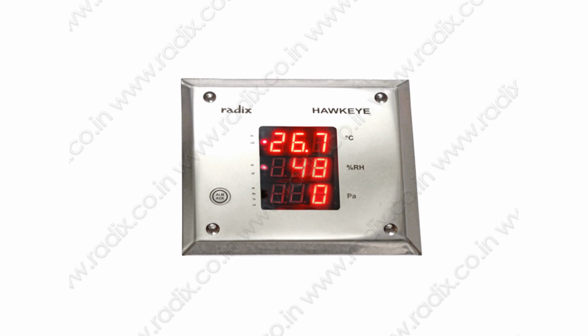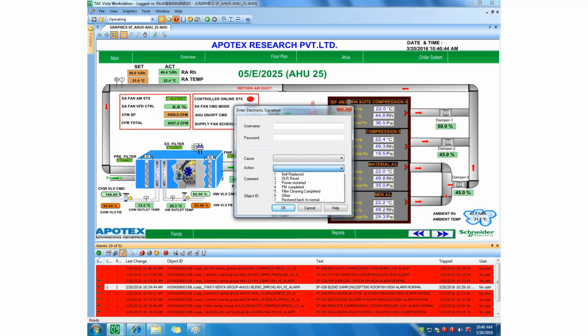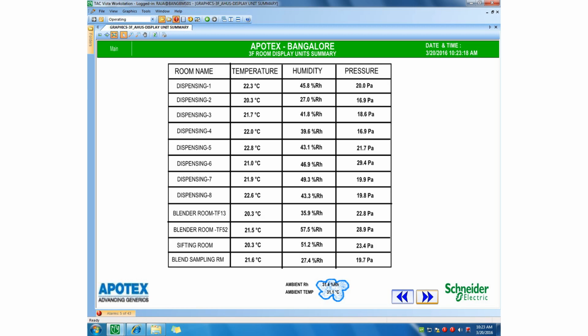All of this data will be recorded back into the front end, where a BMS guy or a BMS will accommodate all the trends and histories of what is going on in what production areas, and all other data from the sensors depicting the temperature, humidity, and the pressure of that certain area. All of these will be recorded and documented in the same way. Documentation is key when it comes to pharmaceutical operations.